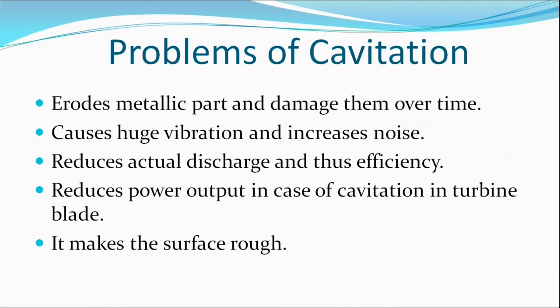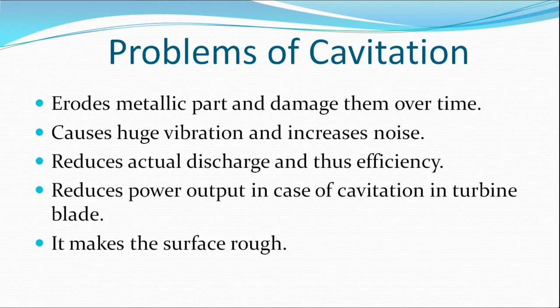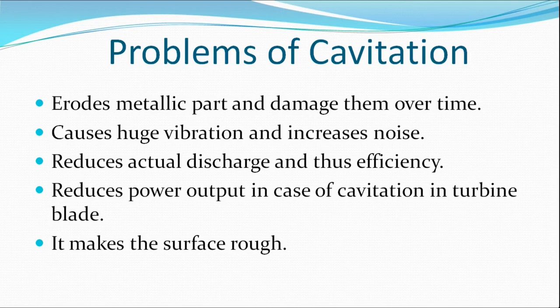Problems of cavitation: Cavitation erodes metallic parts and damages them over time, causing huge vibration and increased noise, which reduces efficiency. In the case of submarines, noise may hamper secret missions. Cavitation also reduces actual discharge and thus efficiency — the bubbles occupy volume with no discharge, so final discharge is decreased. In turbines, cavitation reduces power output because bubble formation means less water hits the turbine blade, causing less energy transfer, less rotation, and less power output. Cavitation also makes the surface rough, as seen in the previous picture.